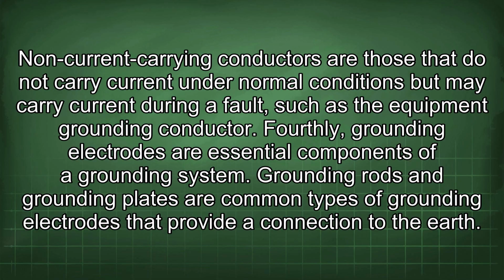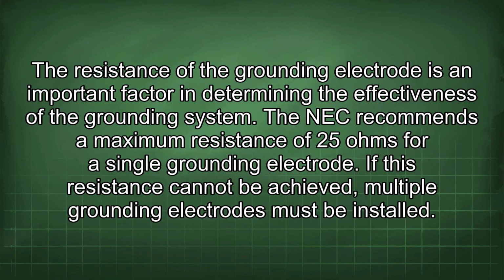Fourthly, grounding electrodes are essential components of a grounding system. Grounding rods and grounding plates are common types of grounding electrodes that provide a connection to the earth. The resistance of the grounding electrode is an important factor in determining the effectiveness of the grounding system. The NEC recommends a maximum resistance of 25 ohms for a single grounding electrode.